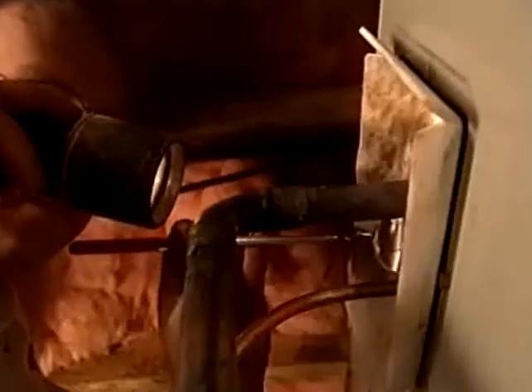Experts recommend using a solder with a high silver content, 15% at the minimum for copper-to-copper connections, and 45% for copper-to-steel connections. The better the solder is, the less likely it is that impurities will find their way into the lines.